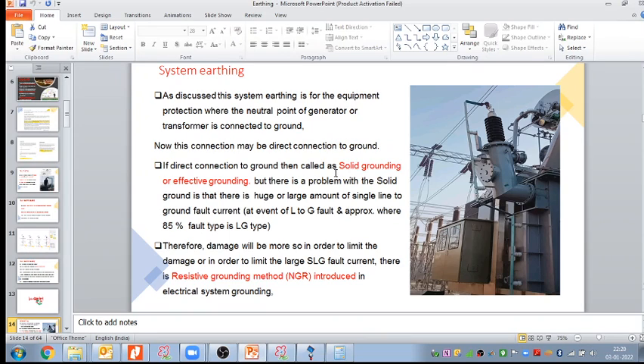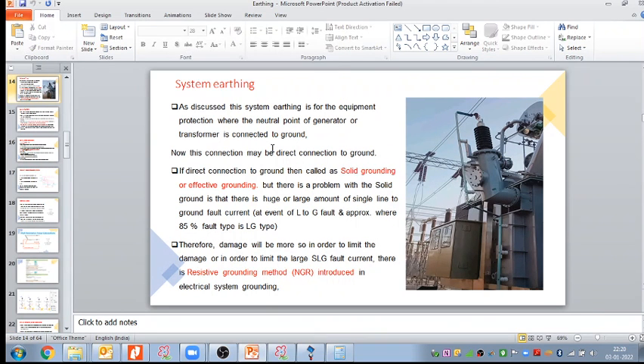Okay, so now coming back to system earthing, as we have discussed, there are two types of earthing, system and equipment earthing. The system earthing is for equipment protection, where the neutral point of the generator or transformer is connected to the ground. This connection may be a direct connection to the ground, as in this snapshot I have taken from the site. You can see the neutral bushing here. This is my earthing conductor, and it is going directly to the ground. There is no intentional other equipment I have put, only this direct connection to the ground. This type of earthing we call solid grounding or effective grounding.